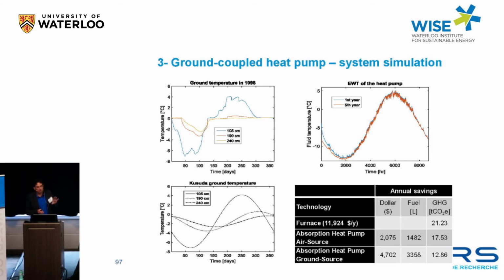This temperature is reproduced with analytical solutions, trying to estimate with basic conductive heat transfer. We neglect here the latent heat effect with freeze and thaw of the water in the soils. And with this background temperature, we use analytical thermal response functions to anticipate what will be the operating temperature of the ground loops. So the temperature is actually below 0 degrees Celsius during winter, but thermodynamically, it's still possible to extract heat.